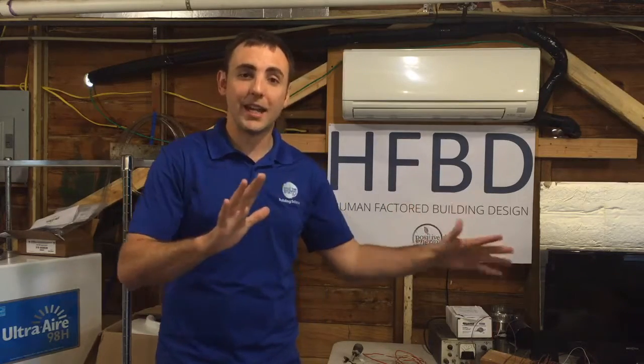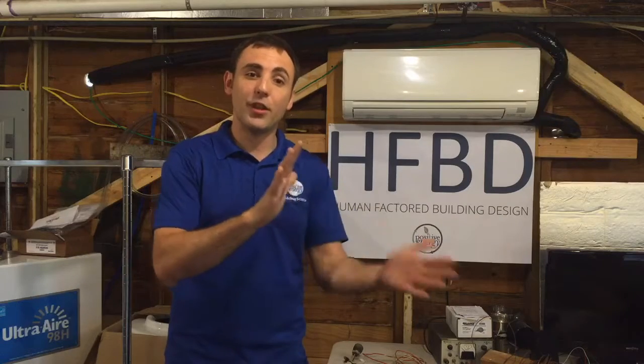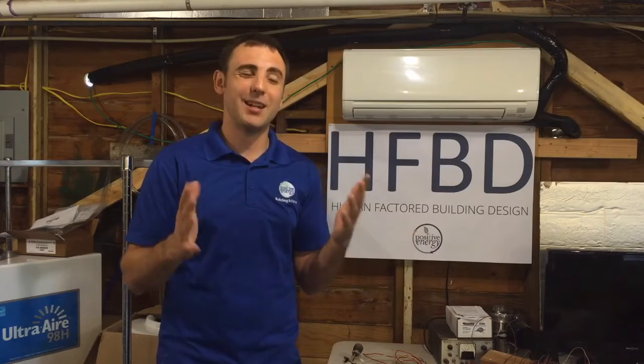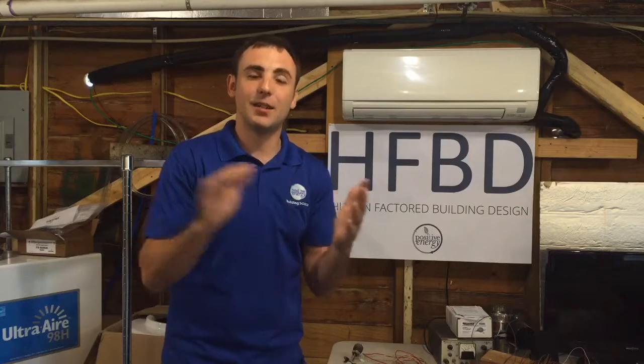The next thing that we can talk about is return side duct leakage, and this often gets overlooked mainly because when you're in the attic and it's supply side duct leakage, you can feel that cold air blowing on you in the attic, and you know that that's not good. But on the return side, you're never really going to be able to feel the air sucking in, and even still, it's going to be lukewarm air that's going in, not cold air that's coming out at you. So you're not really going to feel the effects of return side leakage.